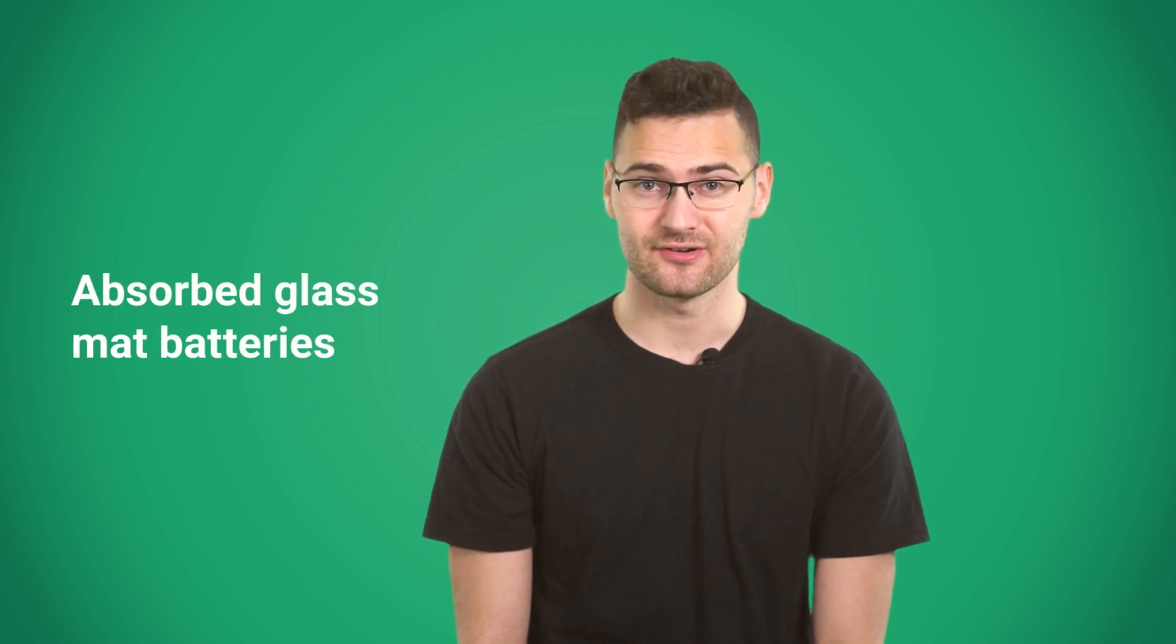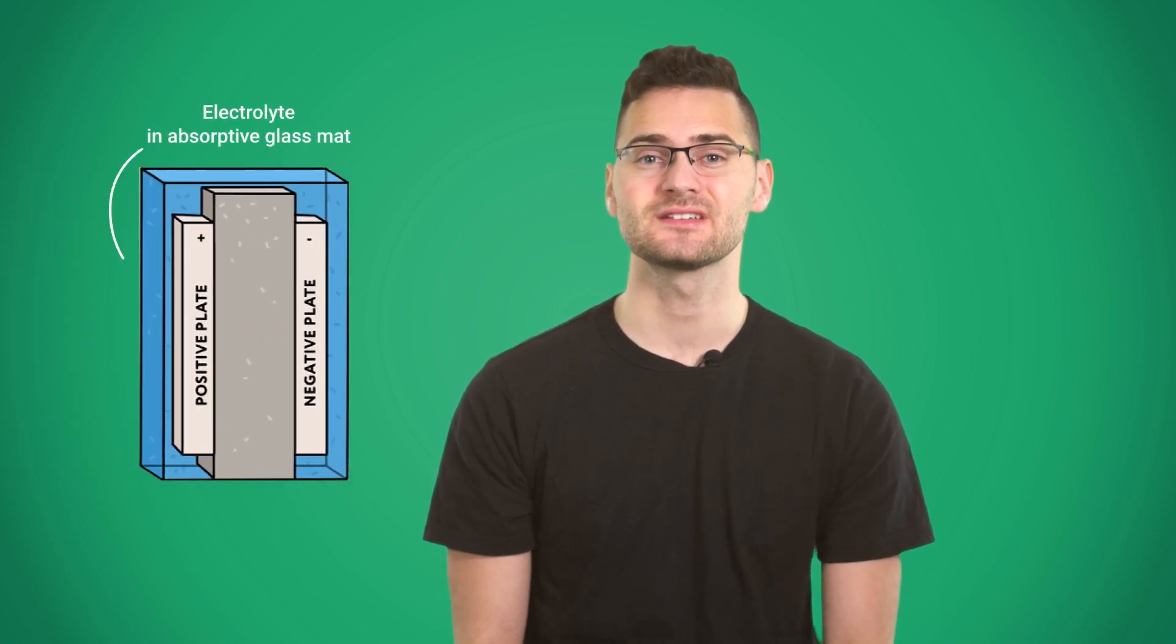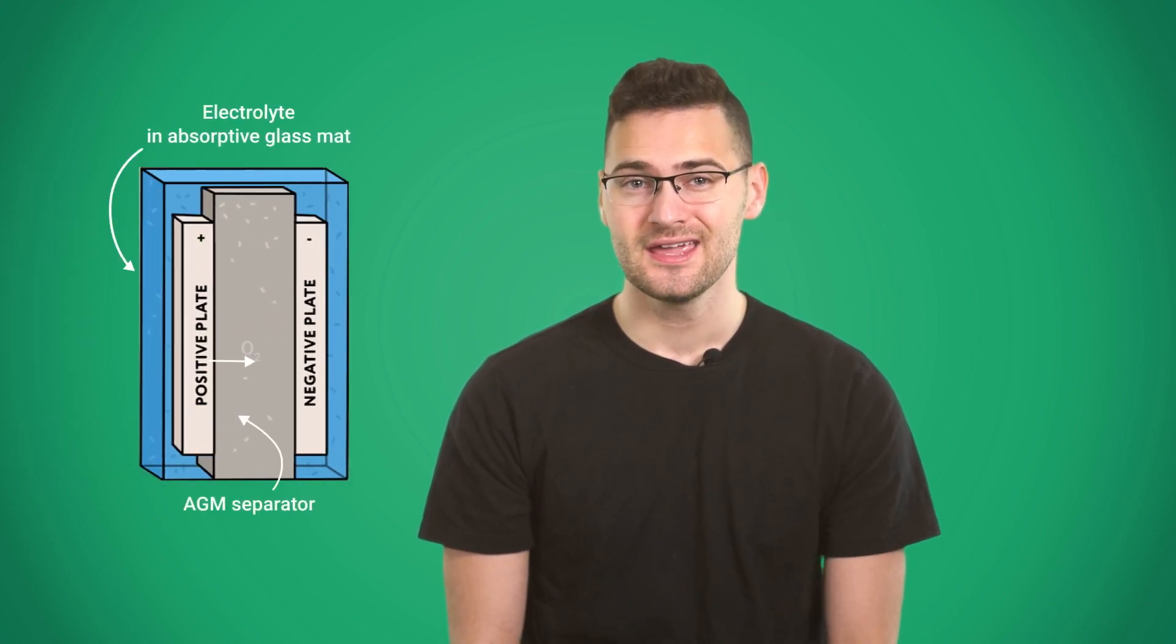The third subtype are AGM, or absorbed glass mat batteries. They're also known as dry cell, because there's no liquid water in them, which makes them safe. It isn't as affected by extreme temperatures as a flooded battery. Its DoD is around 80 percent. Their disadvantage is, again, their vulnerability to overcharging, plus AGM batteries tend to cost twice as much as a good wet cell battery.